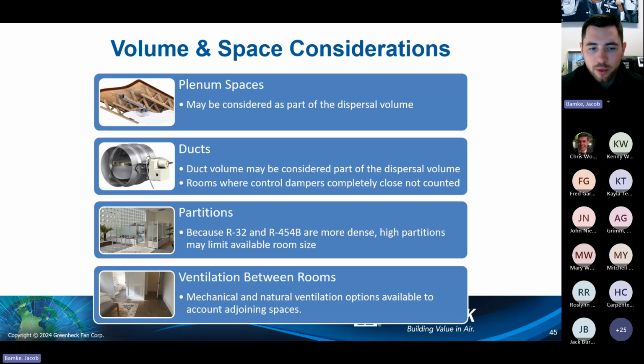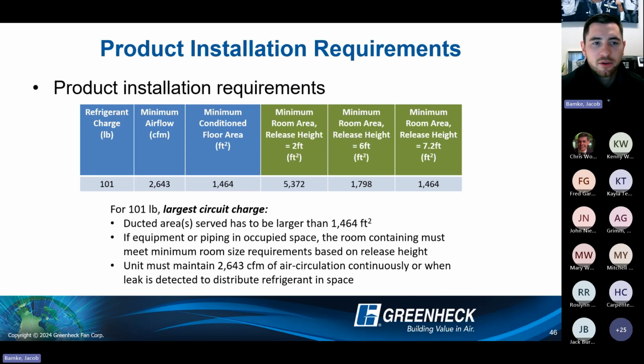And then lastly, ventilation between rooms. Mechanical and natural ventilation options are available to account for those different adjoining spaces as the overall square feet of area that you have to distribute refrigerant to. And so where that comes into play is there are certain installation requirements. This is just one example. Typically, there's a different row in the codes like this for about every pound of refrigerant. In this example, we have a 101 pound circuit. So that's the big thing to keep in mind: it's not based off of total system charge. It's based off of the single largest circuit if you have this refrigerant.